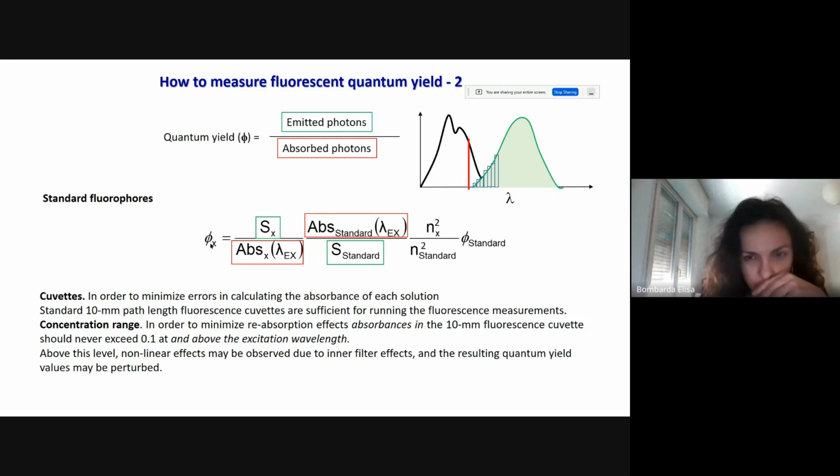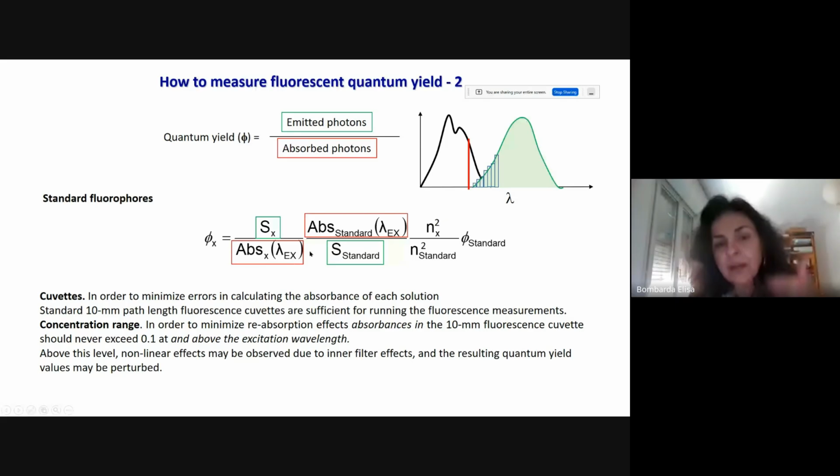Normally it is always much lower. And this parameter is absolute. You measure it with a specific fluorimeter, but this way of calculating practically cancels the specificity of your instrument, and the parameter that you get is something that you can publish and communicate to your community, because it will be obtained the same also with another instrument.